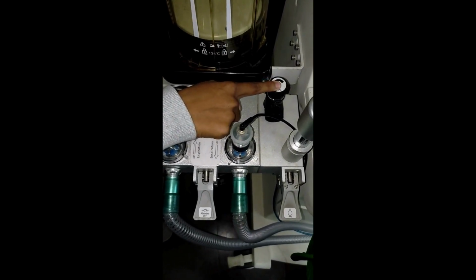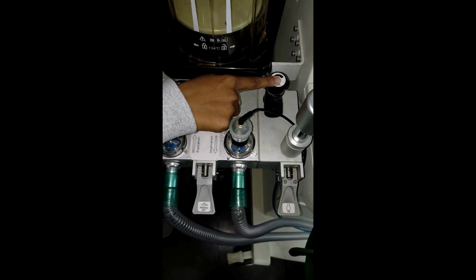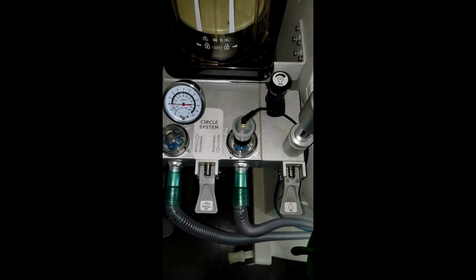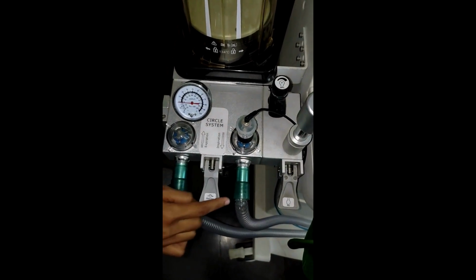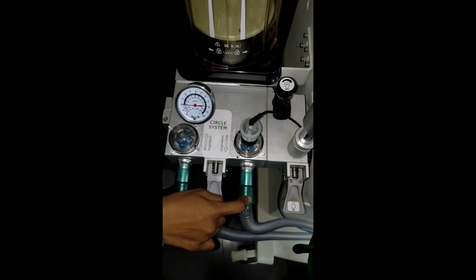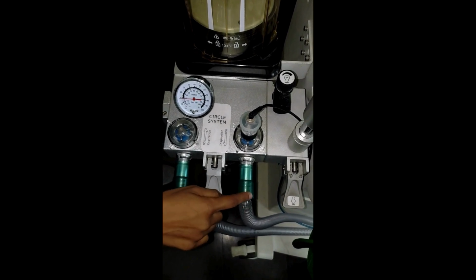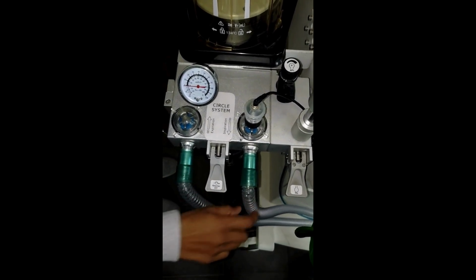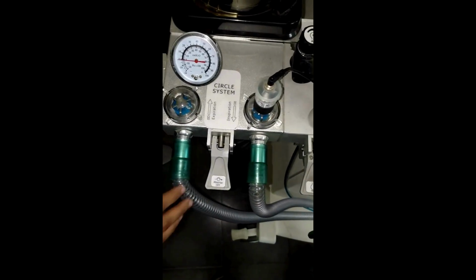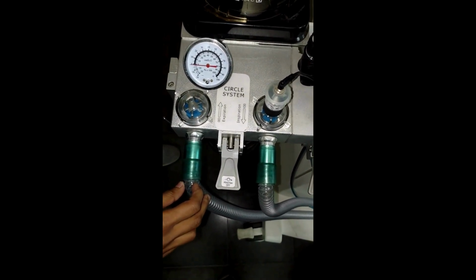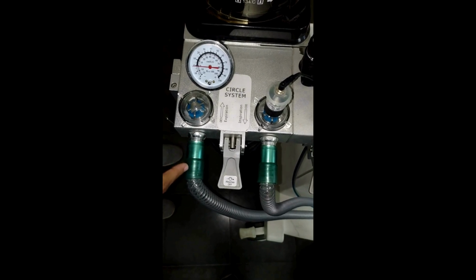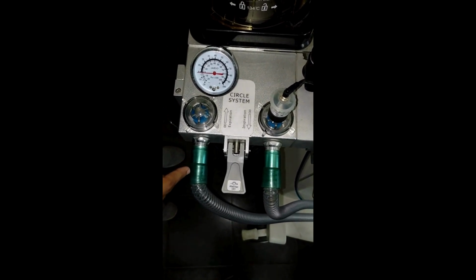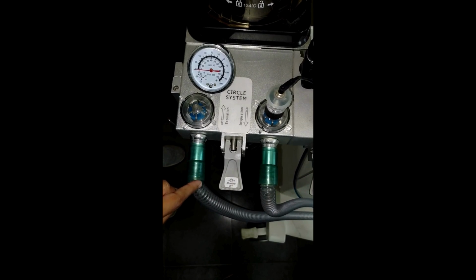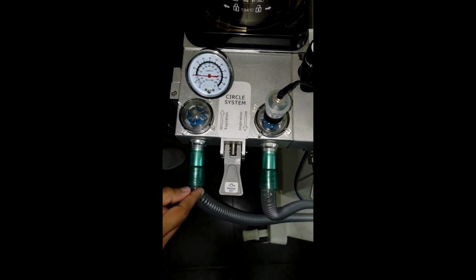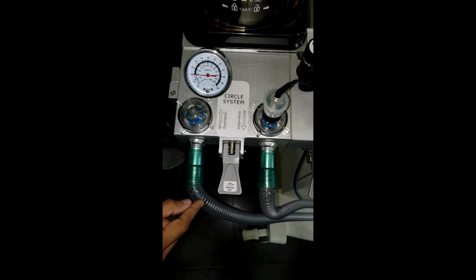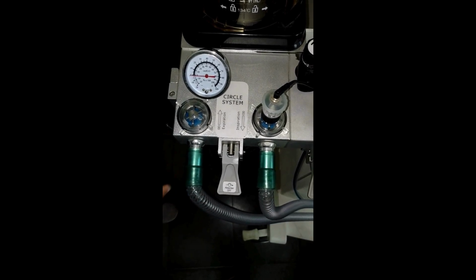The airway pressure valve is used to set the pressure with the help of the knob when the patient is manually ventilated with the help of the breathing bag. Inspiratory port. The delivery of gas to the patient is done by connecting the pipe to the inspiration port of the circle absorber. Expiration port. The expired gas from the patient enters the circle absorber by connecting the pipe from the patient to the expiration port, and the expired CO2 gets absorbed in the breathing system, and the gas is delivered back to the patient mixed with some amount of fresh gas through the inspiration port.